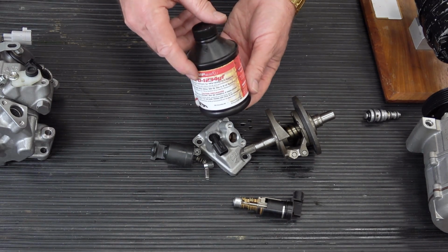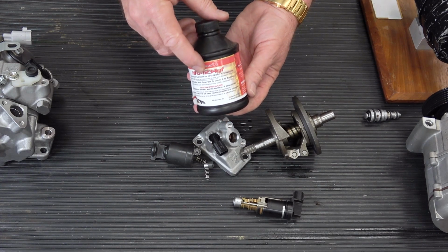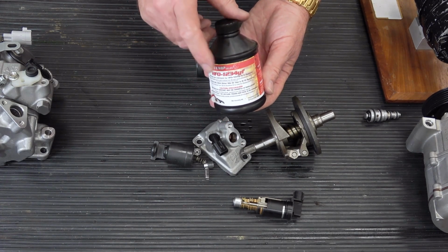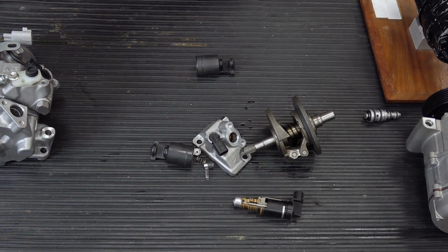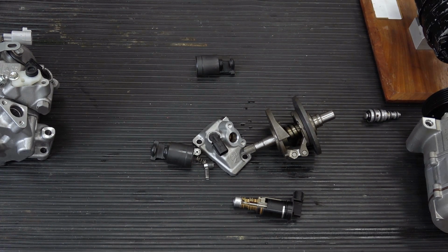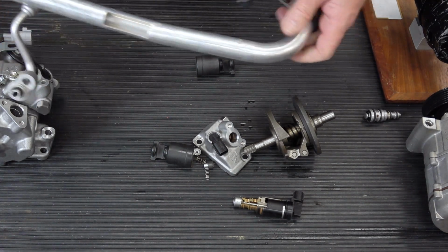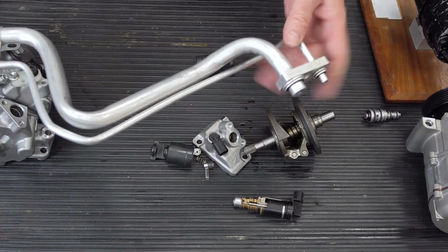Now, the other thing I mentioned as we were getting into the conversation is this oil. This is the YF oil that you need with the new refrigerant, as opposed to the R-134a refrigerant. And the other thing I mentioned in our introduction was the internal heat exchanger. So here is an internal heat exchanger.